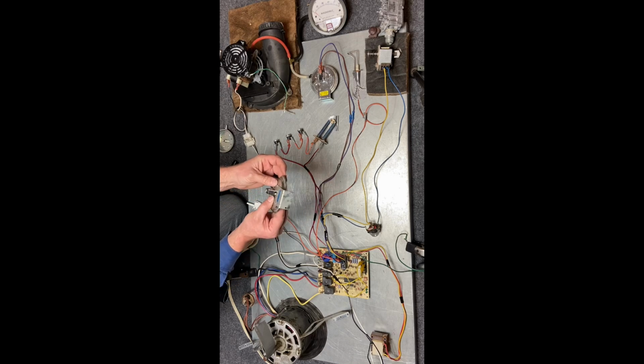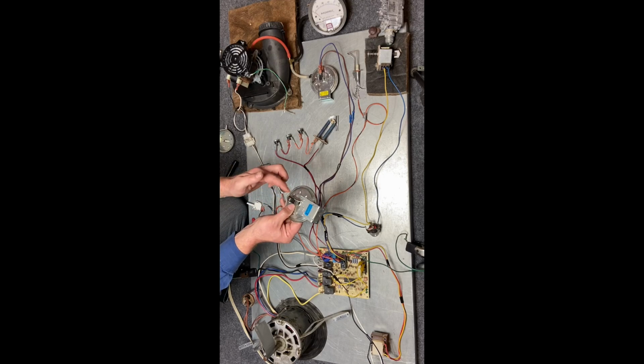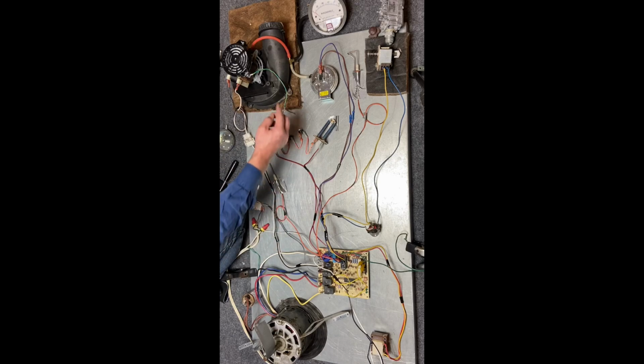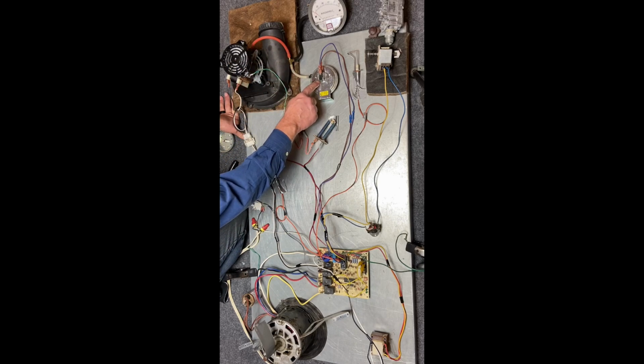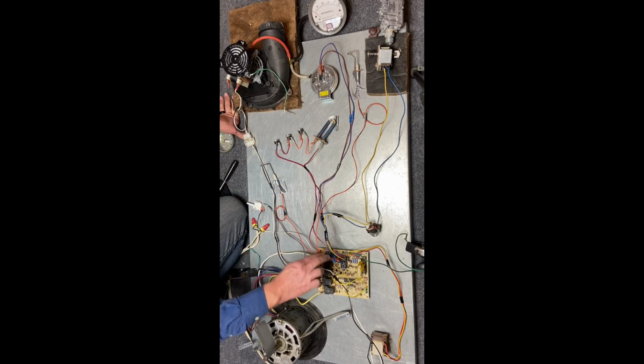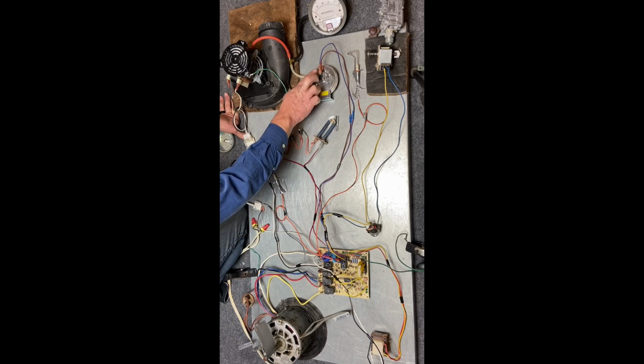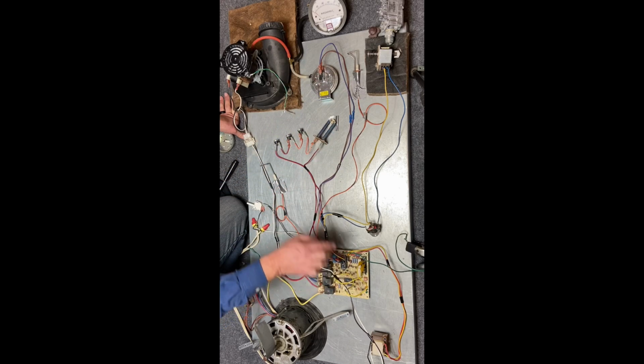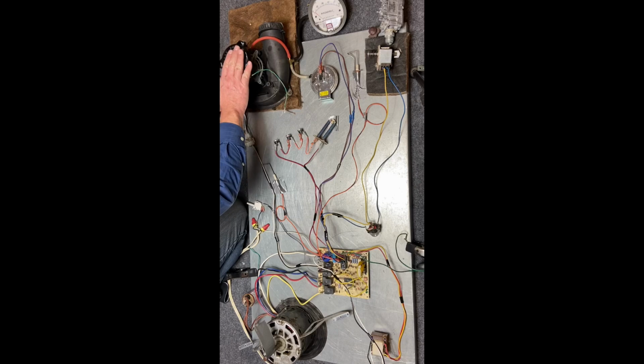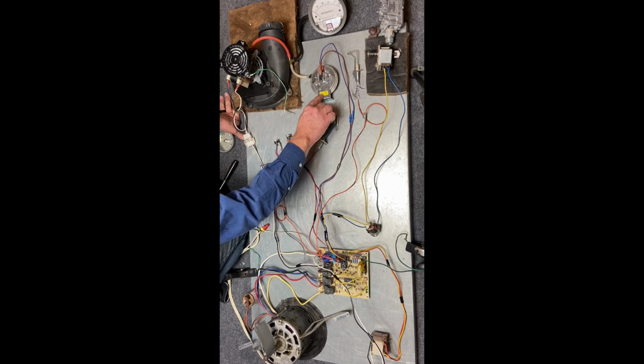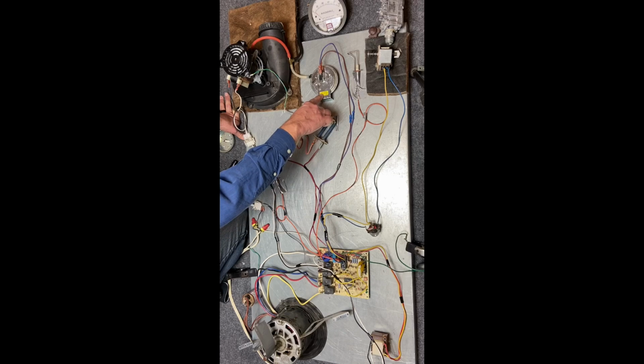So what happens is this switch is normally open and we pull a vacuum, then the switch closes and it just connects these 2 wires. Again, 2 wires. So when this motor runs, it pulls a vacuum to our pressure switch. The switch closes, connects these 2 wires. If we follow these 2 wires, we go back to this plug outlet right here. So this plug is sending 24 volts through one of the wires and is waiting to see if we get 24 volts back to the other wire. This whole job of this switch is to make sure this motor is not just running, but also pulling the proper vacuum or draft through the heat exchanger. This switch is supposed to close at 0.30 inches of water column negative pressure.